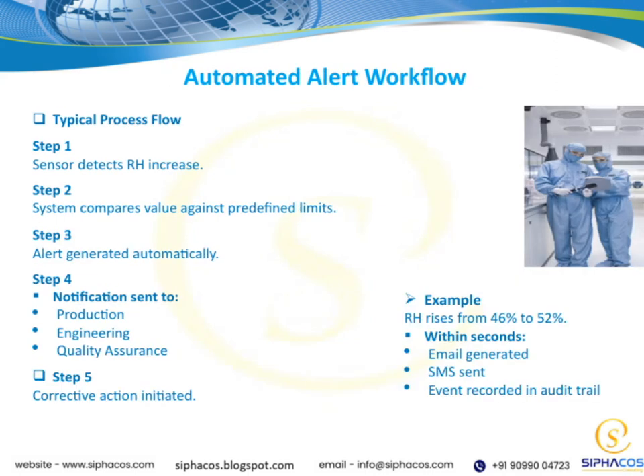Let's walk through a typical process flow when relative humidity rises from 46 to 52%. First, a sensor detects this increase. Then, the system checks the value against preset limits. If it's out of range, an alert is generated automatically. Next, notifications go out to production, engineering, and quality assurance teams. Finally, corrective action is taken. All this happens within seconds. An email is generated, an SMS sent, the event logged, and an automated alert workflow kicks in to keep things running smoothly.